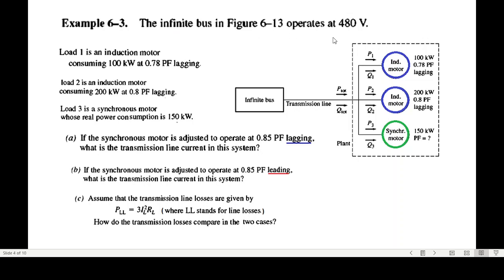The infinite bus in the figure operates at 480 volts. There are three loads: Load 1 with its power and power factor, Load 2 — an induction motor of 200 kilowatts with its power factor, and Load 3 — a synchronous motor with real power 150 kilowatts, but power factor not given. There are three parts: in Part 1 the synchronous motor power factor is 0.85 lagging, in Part 2 it is 0.85 leading, and in Part 3 we compare the transmission line power losses in both cases.